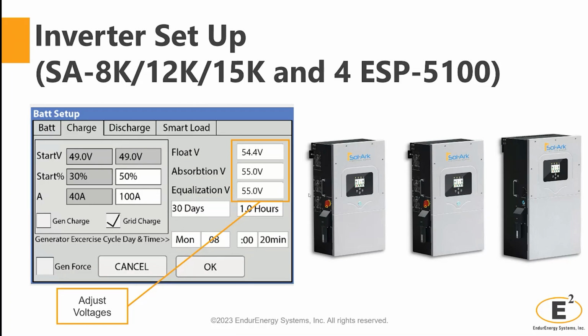From the battery menu, you just click on the charge menu. There you need to make sure you have the proper voltages for both absorption and equalization to guarantee your system works perfectly. For float voltage, you'll have 54.4 volts, and for absorption and equalization, 55 volts. Make sure to set up these voltages as shown for either inverter.